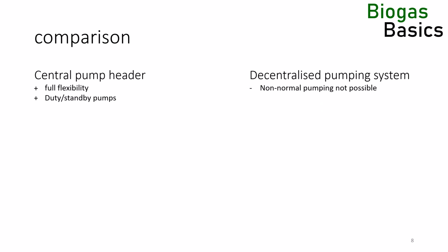This allows maintenance works without plant downtime. Standby pumps in a decentralized system with 7 pumps are not common. However, all the pumps are either 15 or 30 tons per hour. It is possible to hold spare pumps on site and swap them out within a day if they fail. And they will fail less often than in a centralized pumping system because of the lower flow rates, pump pressure, and pumping times. The centralized pump system is common in small-scale agricultural biogas plants, but this system will struggle when more tanks are added to the plant.